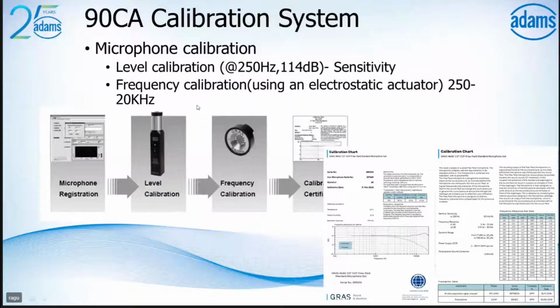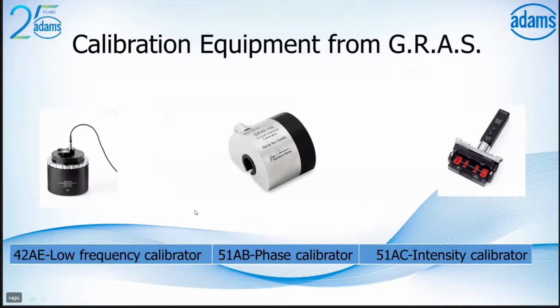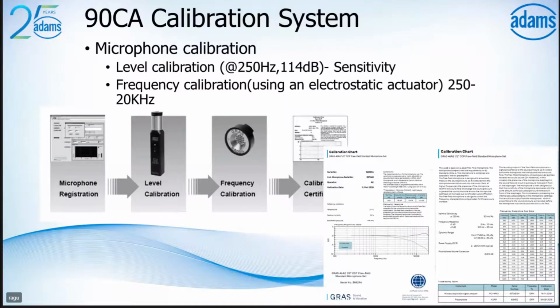The next step is frequency calibration, which is achieved by using an electrostatic actuator. The frequency calibration is performed in the frequency range of 250 Hz to 20 kilohertz. For low frequency calibration, 0.01 Hz to 250 Hz, you will have to use the low frequency actuator from GRAS, which starts from a much lower frequency up to 250 Hz. GRAS also provides you a PC interface and software. At the end of calibration, you get a report like this, with a table, frequency response deviation and a graph.